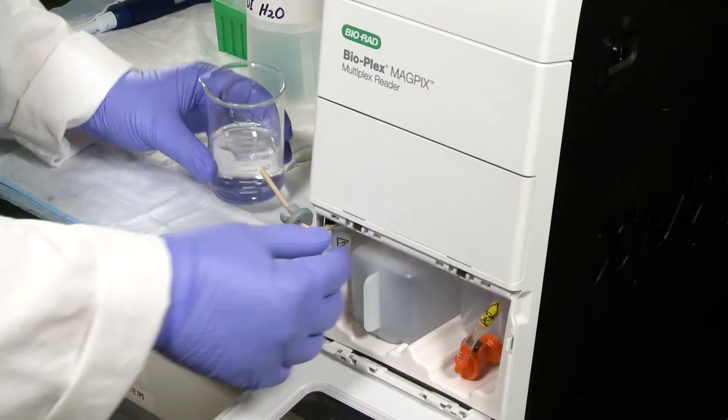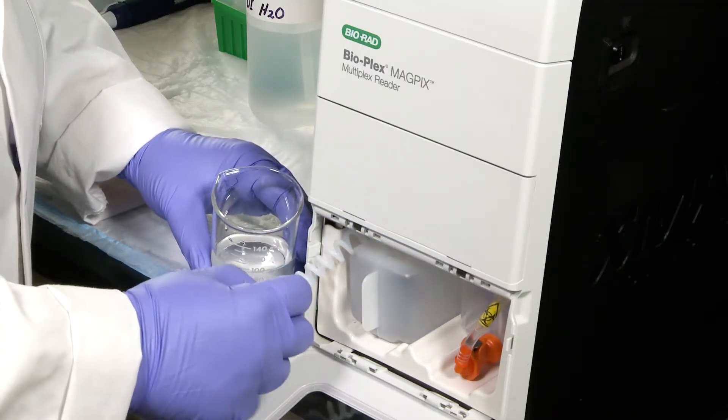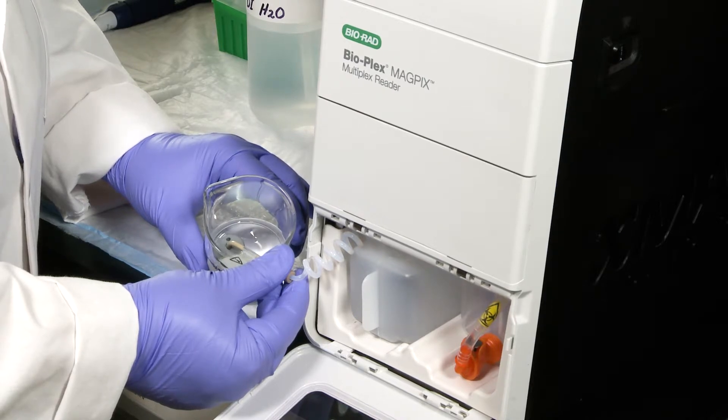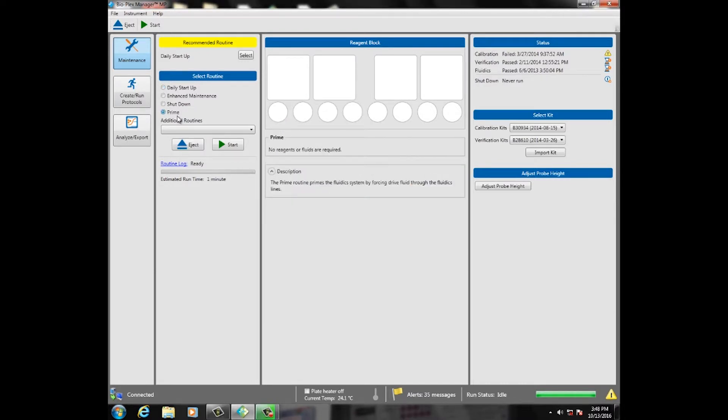Thus, 10 prime routines need about 60 ml of liquid. Remove the drive fluid probe from the bottle and place it into the reagent in the reservoir. You may have to hold it in place with your hand to keep it from slipping back into the instrument. In BioPlex Manager MP software, select the prime routine and click Start. Repeat this procedure 10 times.